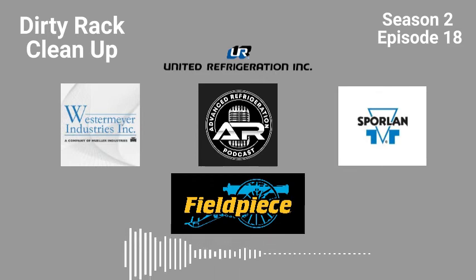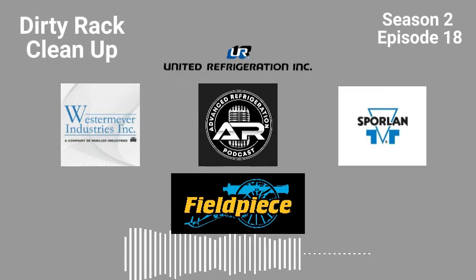Yeah, I'd rather have a finer screen and change the dryers more than have to deal with not getting it. I mean, but again, they will blow out. I've seen them blow out. The Danfoss ones seem to plug up nonstop though. That screen, whatever they have on there, is super fine. The dryers will be super clean, but the screen's doing most of the work.